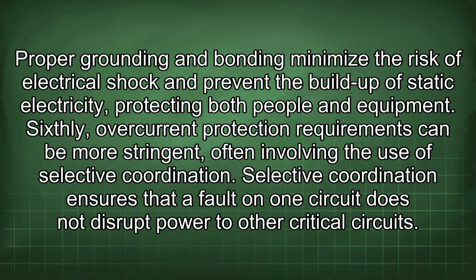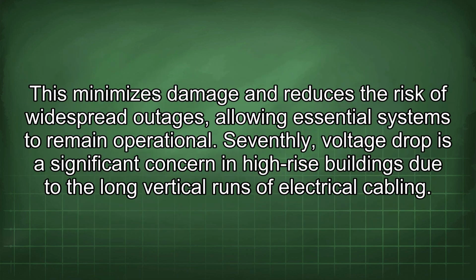Sixthly, overcurrent protection requirements can be more stringent, often involving the use of selective coordination. Selective coordination ensures that a fault on one circuit does not disrupt power to other critical circuits. This minimizes damage and reduces the risk of widespread outages, allowing essential systems to remain operational.